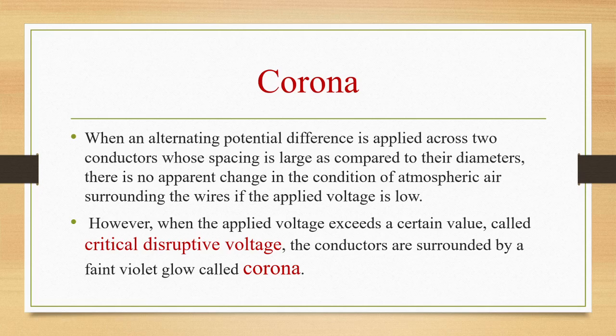Whenever an alternating voltage is applied across two conductors whose spacing is very large compared to their diameters, there is no apparent change in the condition of the atmospheric air surrounding the wires if the applied voltage is low. However, when the applied voltage exceeds a certain value, the critical disruptive voltage, the conductors will be surrounded by a faint violet glow, which is called corona.